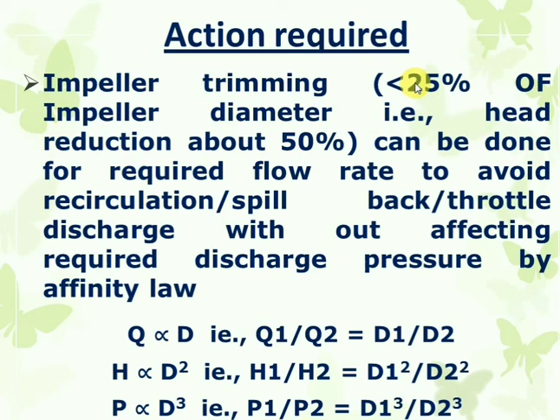Why should we not exceed 25% trim? Because efficiency will drastically come down and head reduction will be drastic — falling below 50% — which will affect the required discharge pressure. Internal circulation will increase, cavitation will be more, impeller and casing pitting will be more, and energy loss will be more. Compared to the energy gain, the pump life will also come down. So you should not trim the impeller greater than 20-25% of its original diameter.